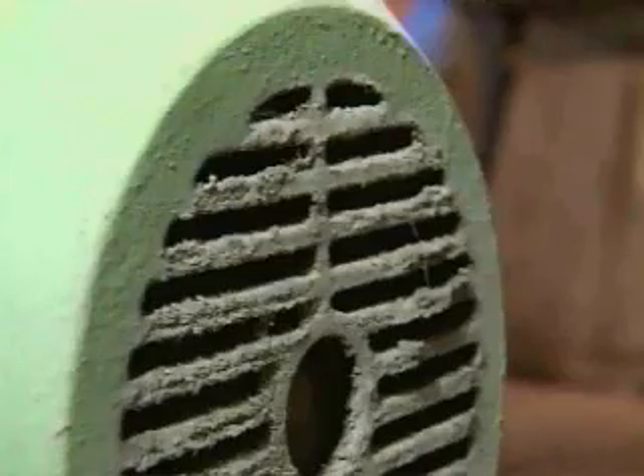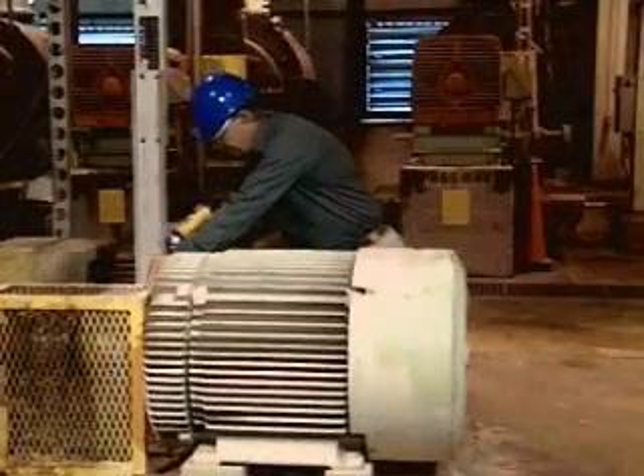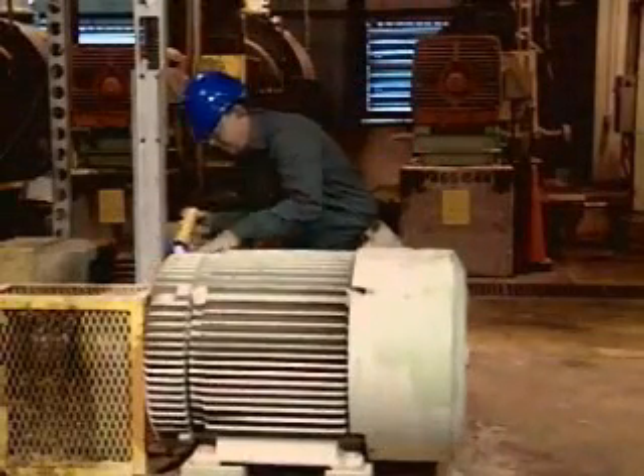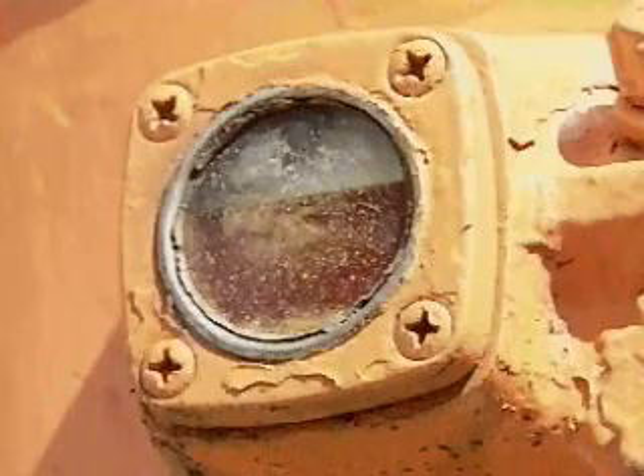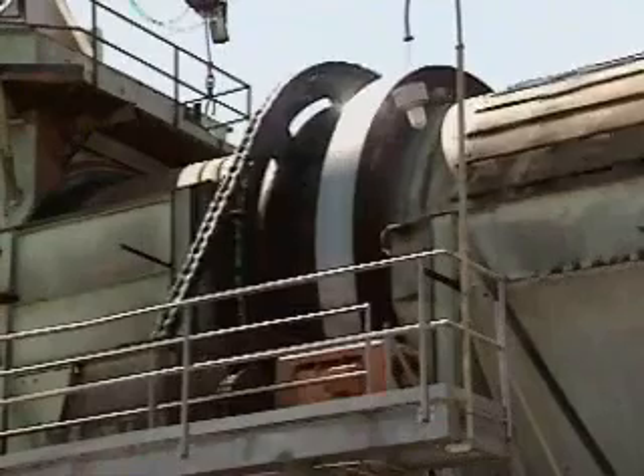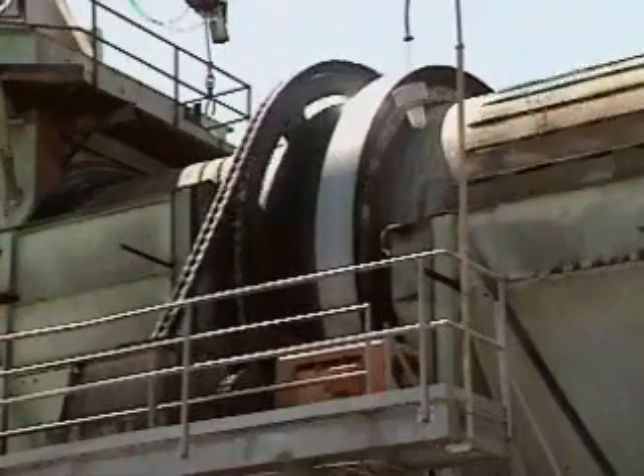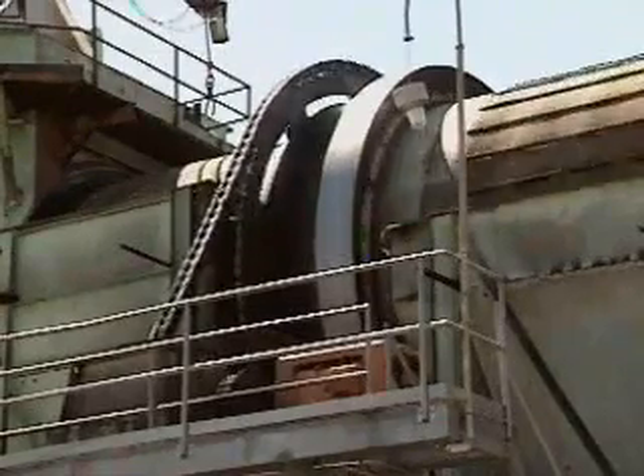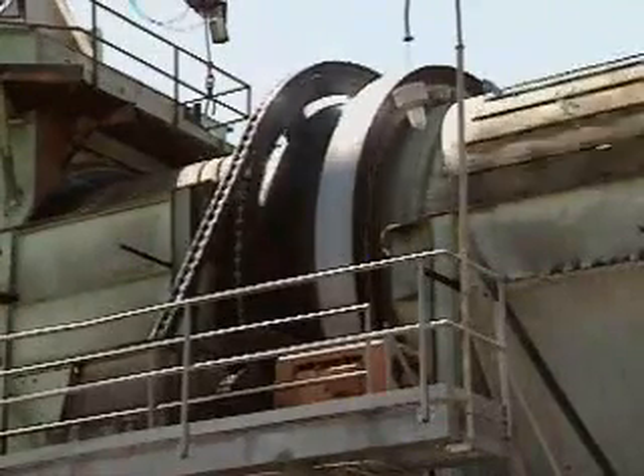Inspect the motor for overall cleanliness. Look for dirt, dust, and grease, or anything else that blocks the motor's screens and vents. Inspect lubricated areas of the motor, such as the bearings, for evidence of leakage and dripping. Visually check oil levels. If possible, start the motor to find out if it comes up to speed in the normal amount of time. Select Next to continue.